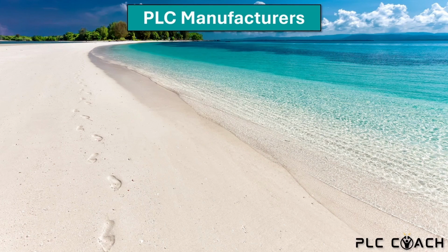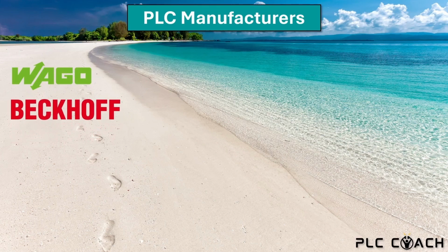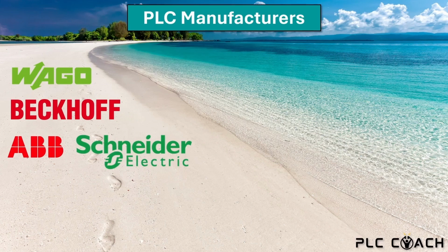In Germany, for example, the manufacturers Wago and Beckhoff are well known. Wago produces its own PLCs but uses the independent software Codesys for programming. Beckhoff produces industrial PCs which can also perform the tasks of a PLC. Programming is done using the software TwinCAT. Other well-known manufacturers are ABB from Switzerland and Schneider Electric from France.